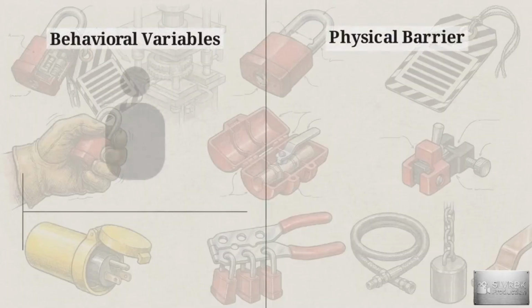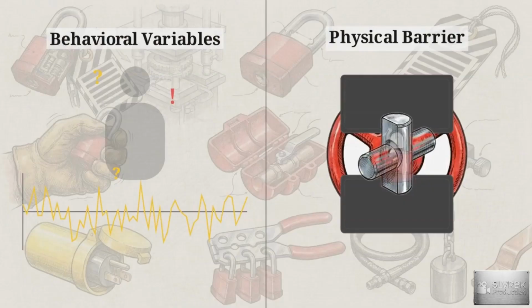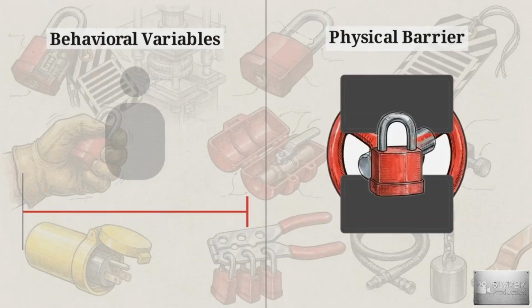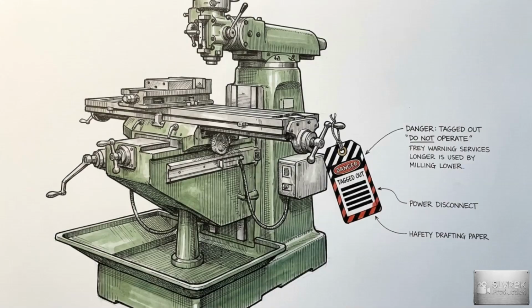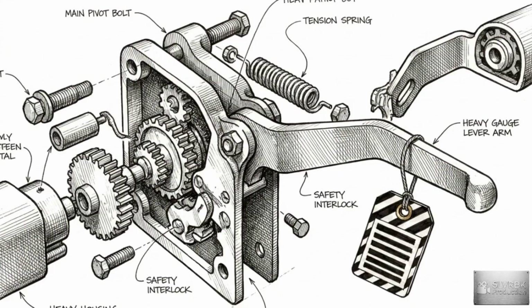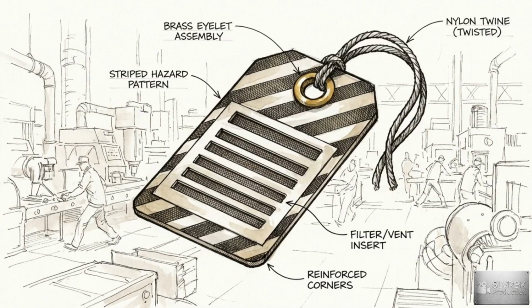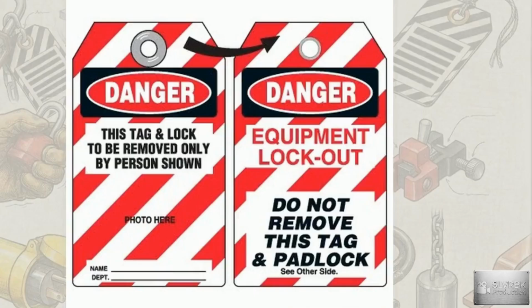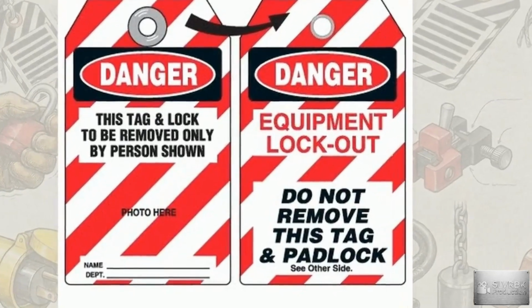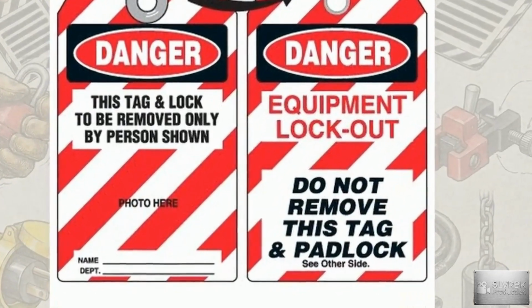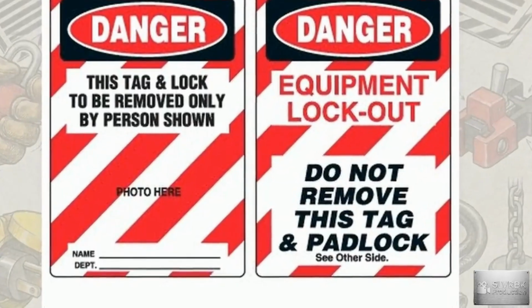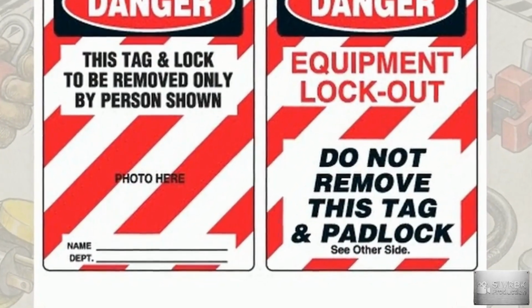By substituting human behavioral variables with an uncompromising physical barrier, lockout serves as the most effective method for controlling hazardous energy. Tagout operates on a different premise. A tag is strictly a prominent visual warning. It provides absolutely no physical restraint on the machinery it is attached to. To ensure these warnings are universally understood across a busy floor, tags must be rigidly standardized by color, shape, and print. They require high-contrast designs and explicit instructions like "do not start" or "do not energize."